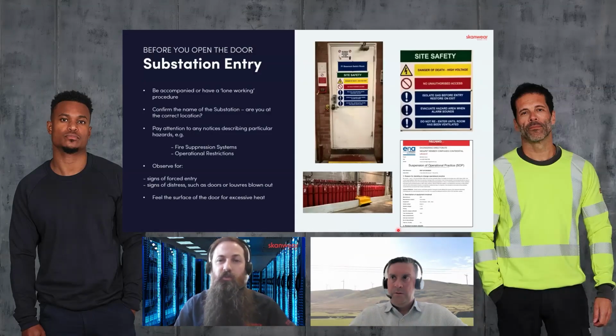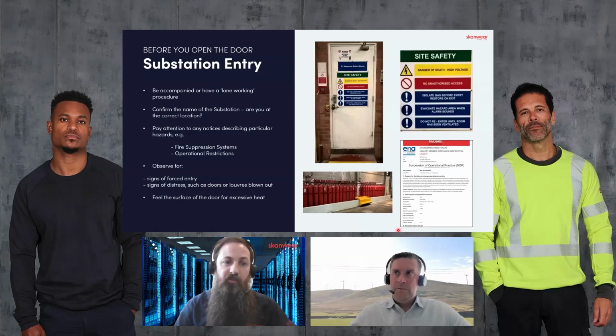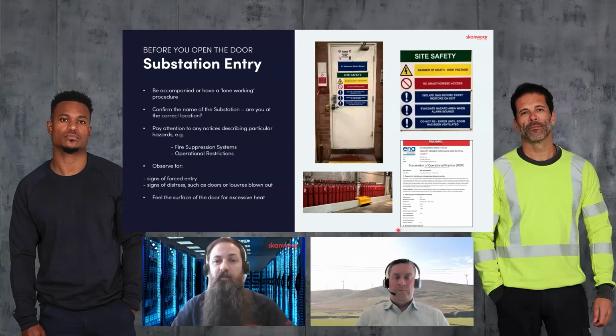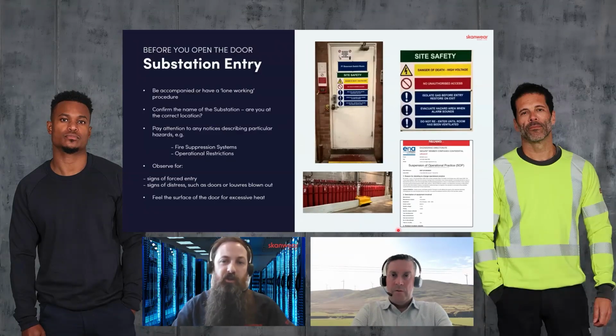Substations are not normally on the normal route. They're tucked away, in the middle of nowhere, up on mezzanines. So it's really important to let people know where you are. Confirm the name of the substation, and confirm you're at the right place. Depending on the environment, sometimes substations are directly next door to each other, and a lot of the switchgear is very common. If you're in renewables, things like wind turbines all look exactly the same, other than a differentiation on the door or naming convention. So make sure you're in the right place.